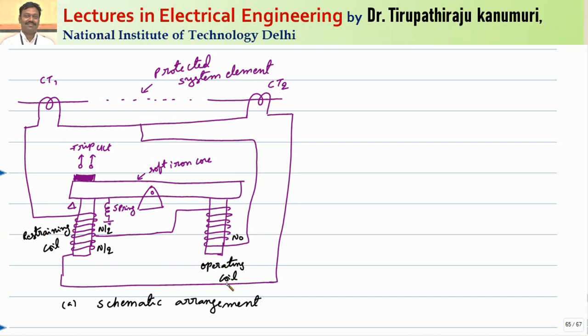The operating coil produces the operating force. The operating coil is connected between the equipotential point of the first CT, and from the operating coil the connection goes to the center point of the restraining coil. The restraining coil is connected across the two CT secondary points. The current from CT1 is I1 and from CT2 is I2.